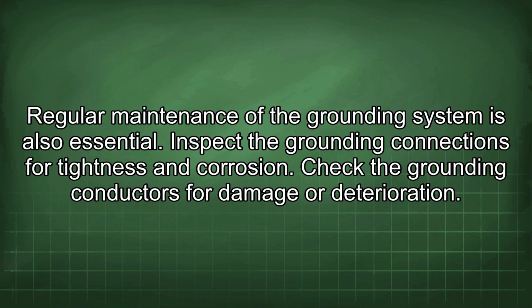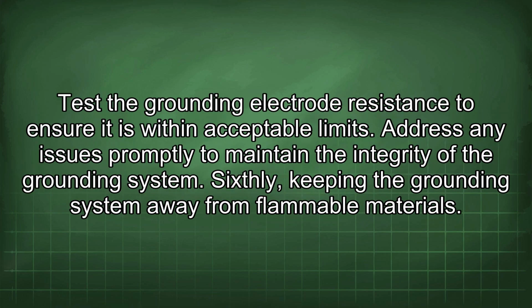Inspect the grounding connections for tightness and corrosion. Check the grounding conductors for damage or deterioration. Test the grounding electrode resistance to ensure it is within acceptable limits. Address any issues promptly to maintain the integrity of the grounding system.